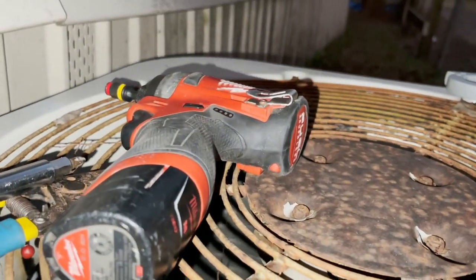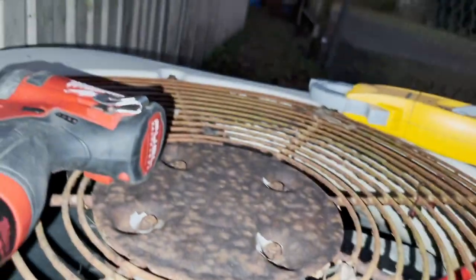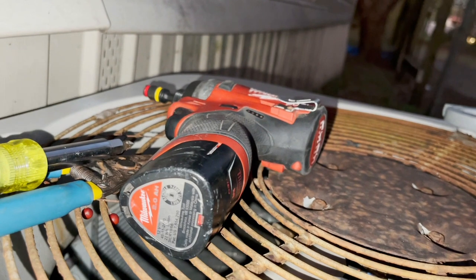Okay, it's running but we have no outdoor fan motor. I'm going to pull that out and find something to try to spin it with — I can get a meter lead down there, it's not that far. Oh no, she's bound up. Yeah, that motor is bound up real tight.